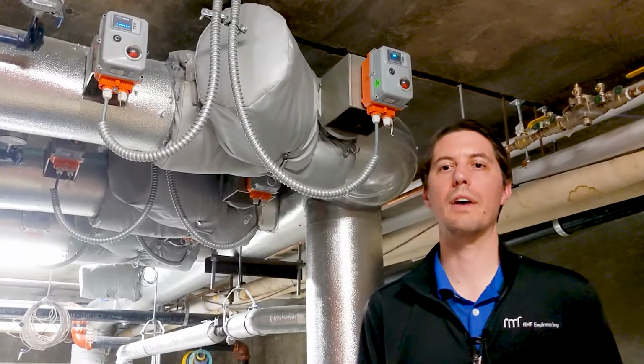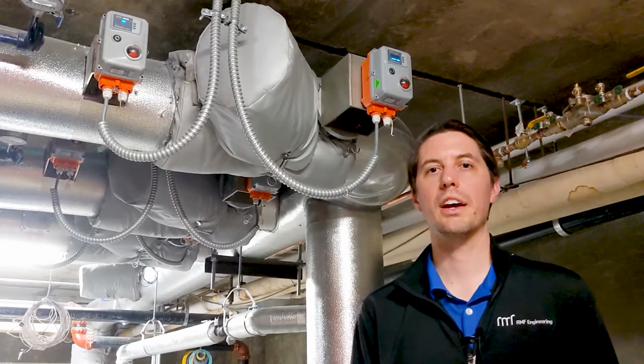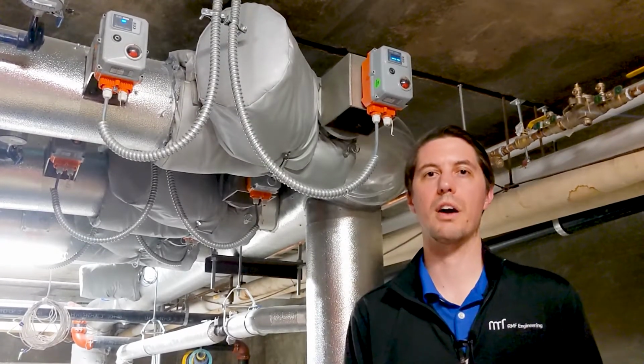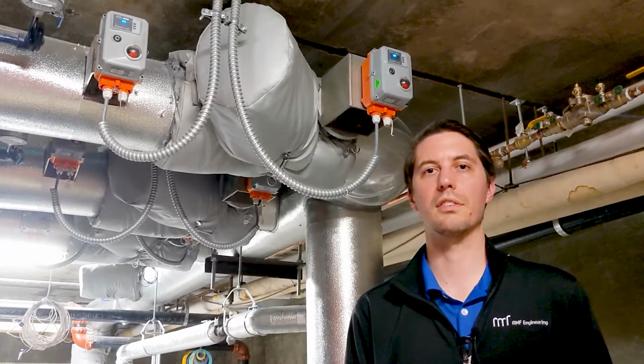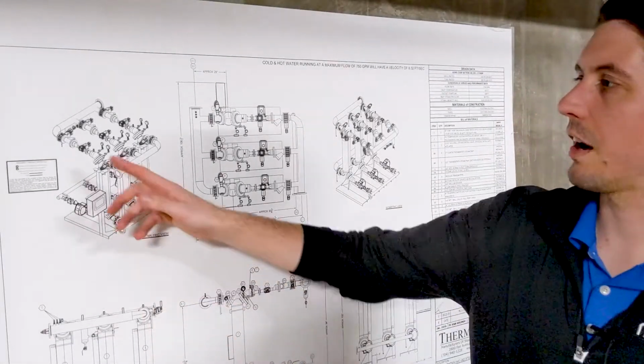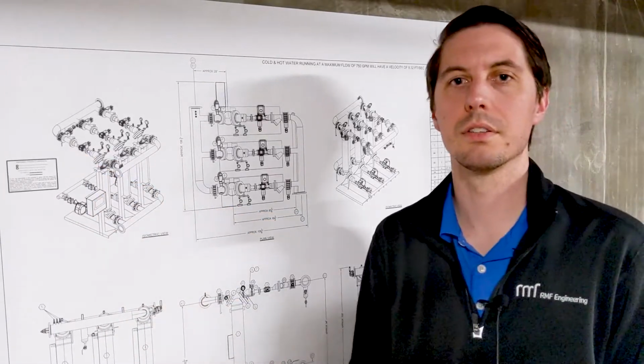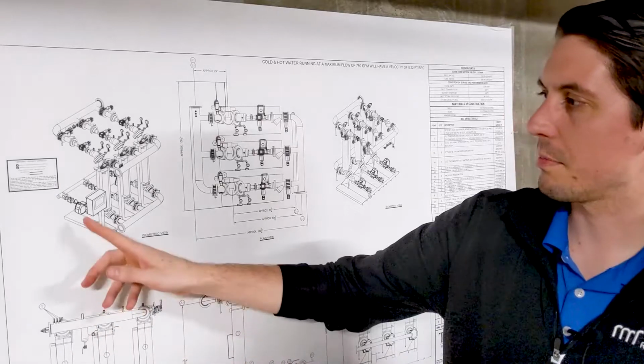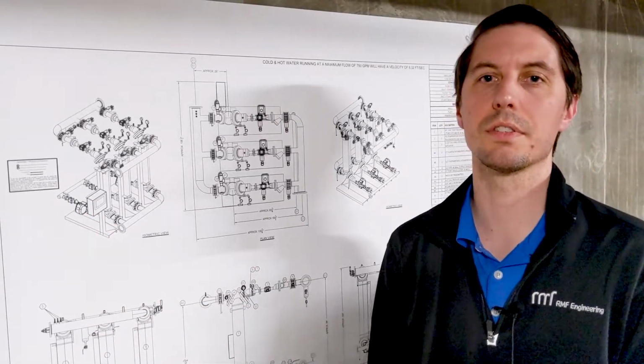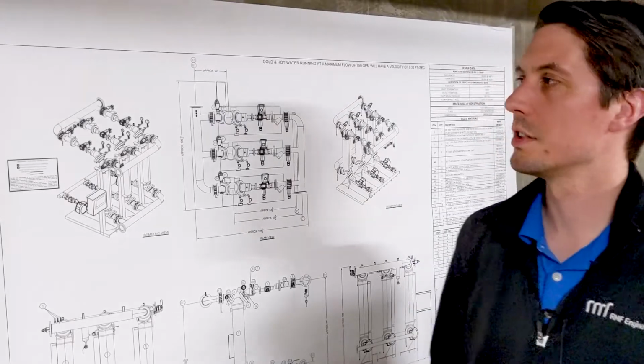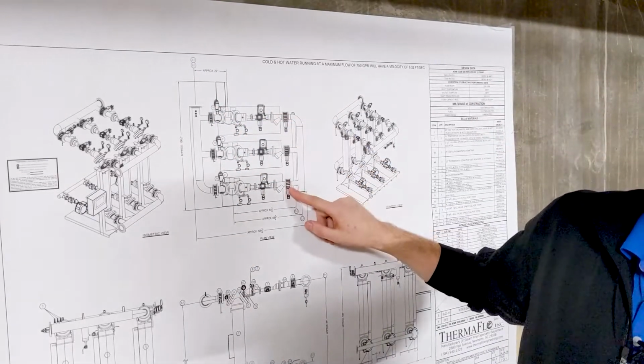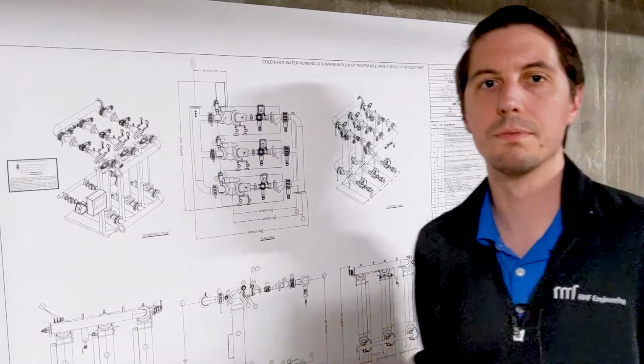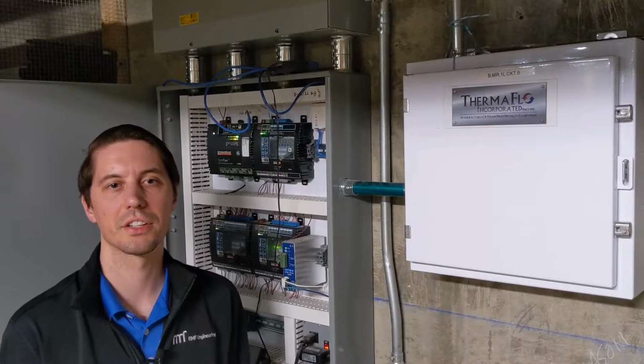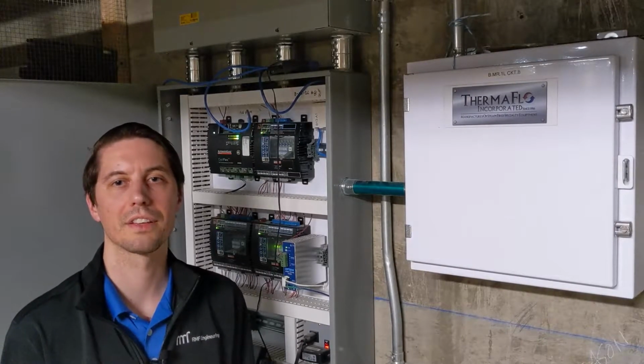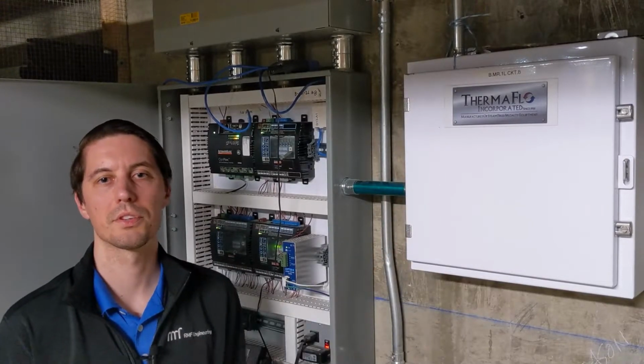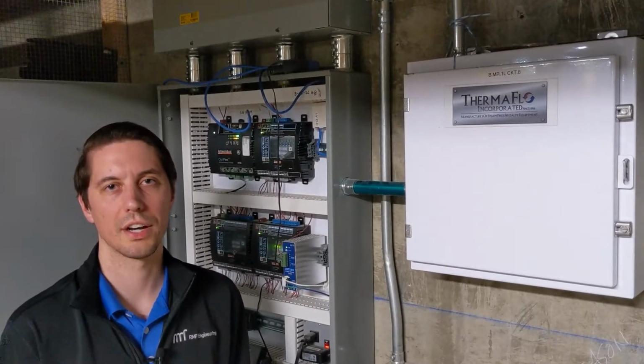The skid is equipped with control valves, transmitters, and a BAS panel. The BAS panel is connected to the Cornell Controls network for monitoring these valves and transmitters, and receiving the status of equipment. These steam valves up top reduce steam pressure to 17 psig, and these traps at the bottom help ensure that all latent heat is transferred to the hot water loop. All this takes place on a 5-foot by 7-foot skid that is no more than 9 feet tall. One of the nice features of this type of heat exchanger is controllability. The control panel reports back to the campus the valve positions, temperature conditions, and equipment status at all times.